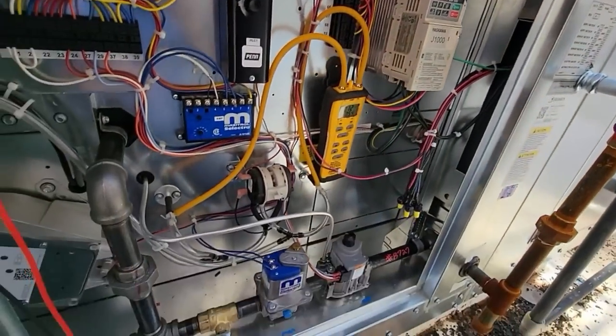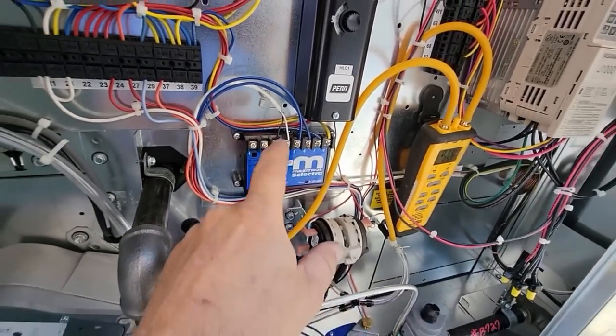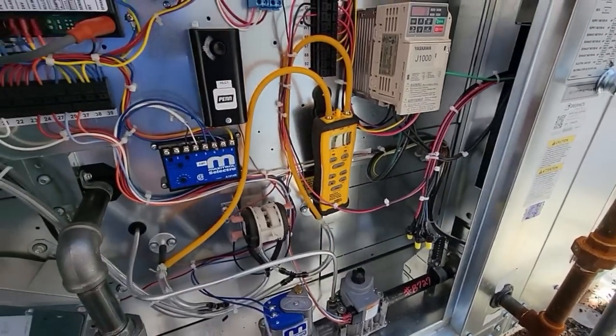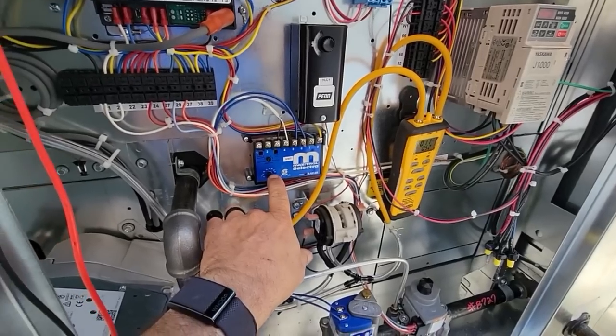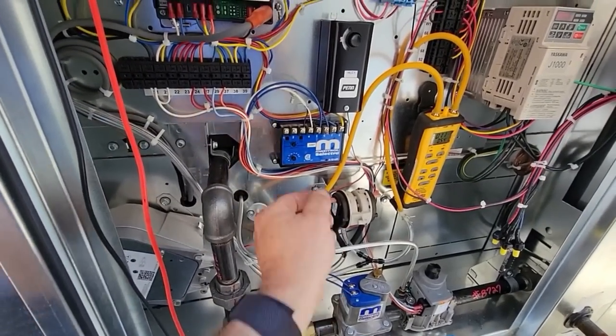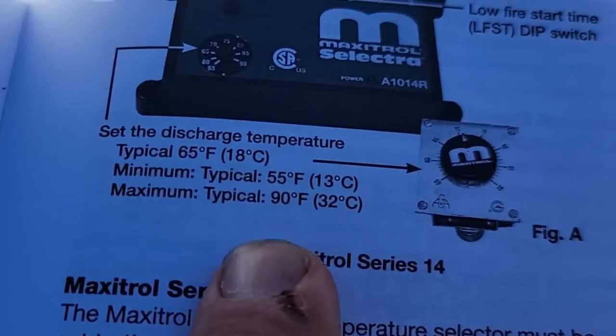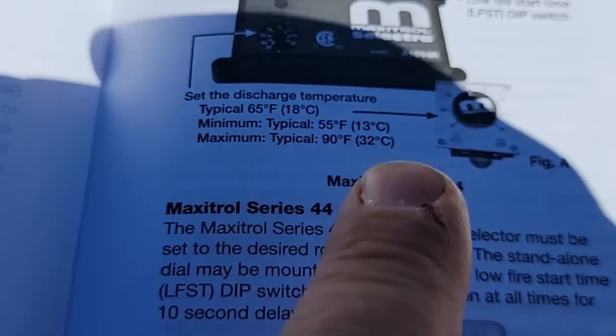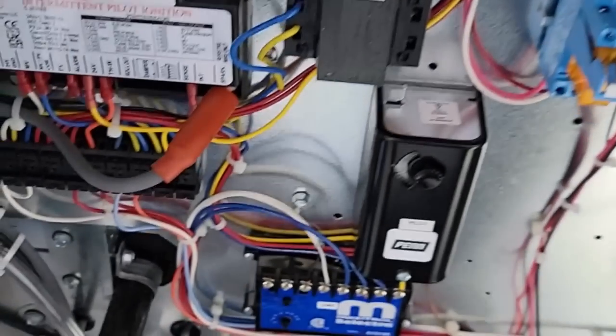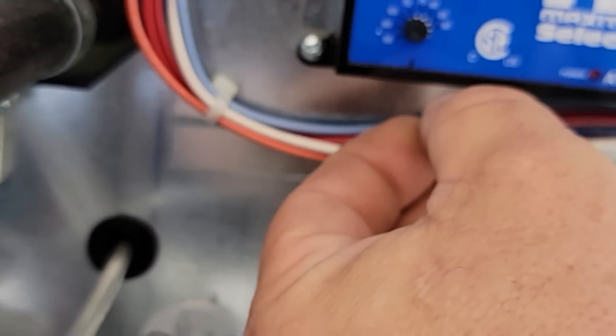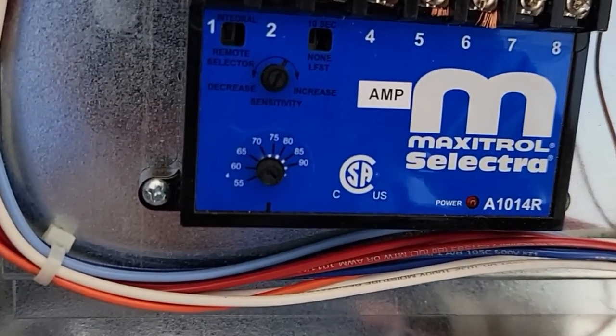Good deal. We got that wire hooked back up on 3. We'll go ahead and take our meter off. I just got to double check our setting here, and then we'll be done here in a little bit. That right there is the desired discharge temperature. 65 is typical, which I can agree with. So we'll take that down to 65. There we go.